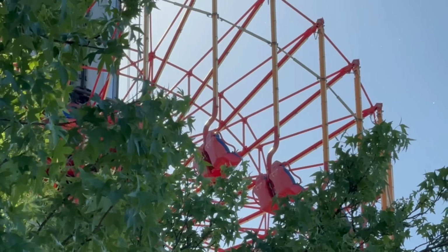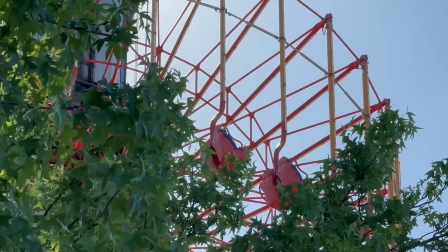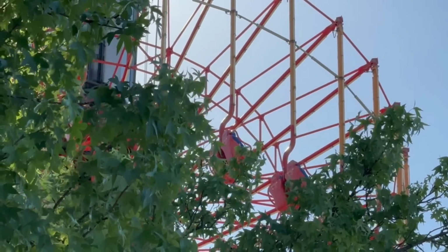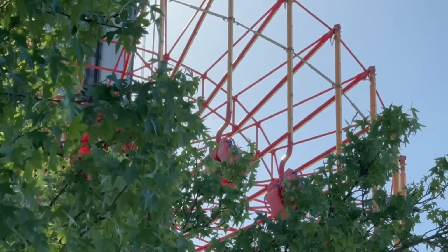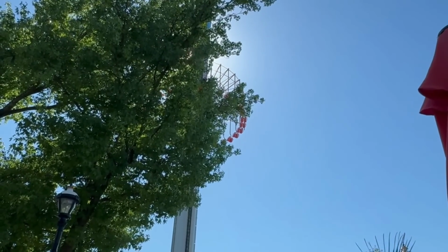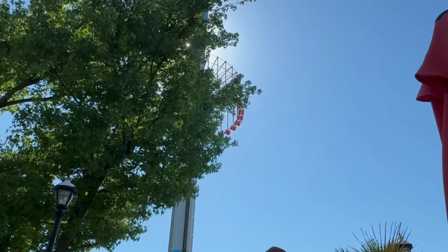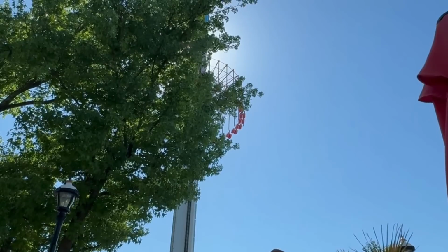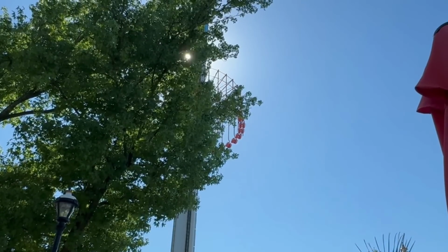Swing rides and stuff like that, where they have to keep speed and monitored position between a certain little window, if for some reason the position comes out of that window, again, it doesn't know why, it goes right to that fault level 2. So the warnings, you pretty much rarely see them on rides. The fault level ones that are just like a motion stop and easy to reset, you see those a little bit, not too much. They're typically always at fault level 2.